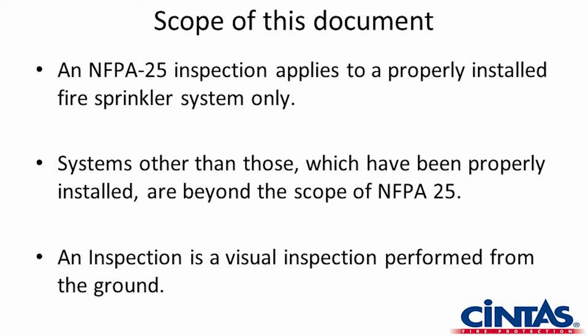The visual inspection is performed from the ground. When we go in and look at sprinkler heads, many times we provide a quote to correct. We found 5 sprinkler heads that we could see. Since that inspection was conducted from the ground, once we get ladders in and have a crew in, many times we find that there are more sprinkler heads that we were not able to see from the ground, and you might receive a follow-up quote for a repair. It's very frustrating, I know, but that's how the standard was written.